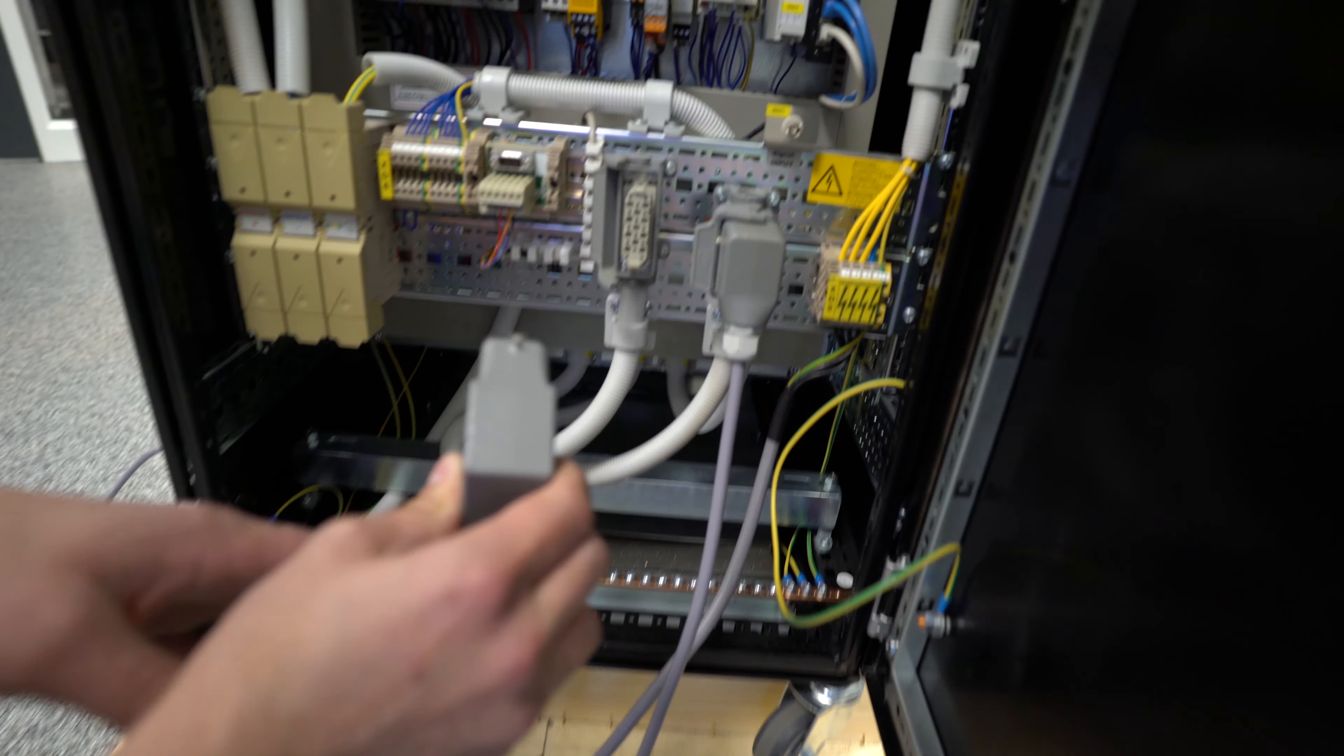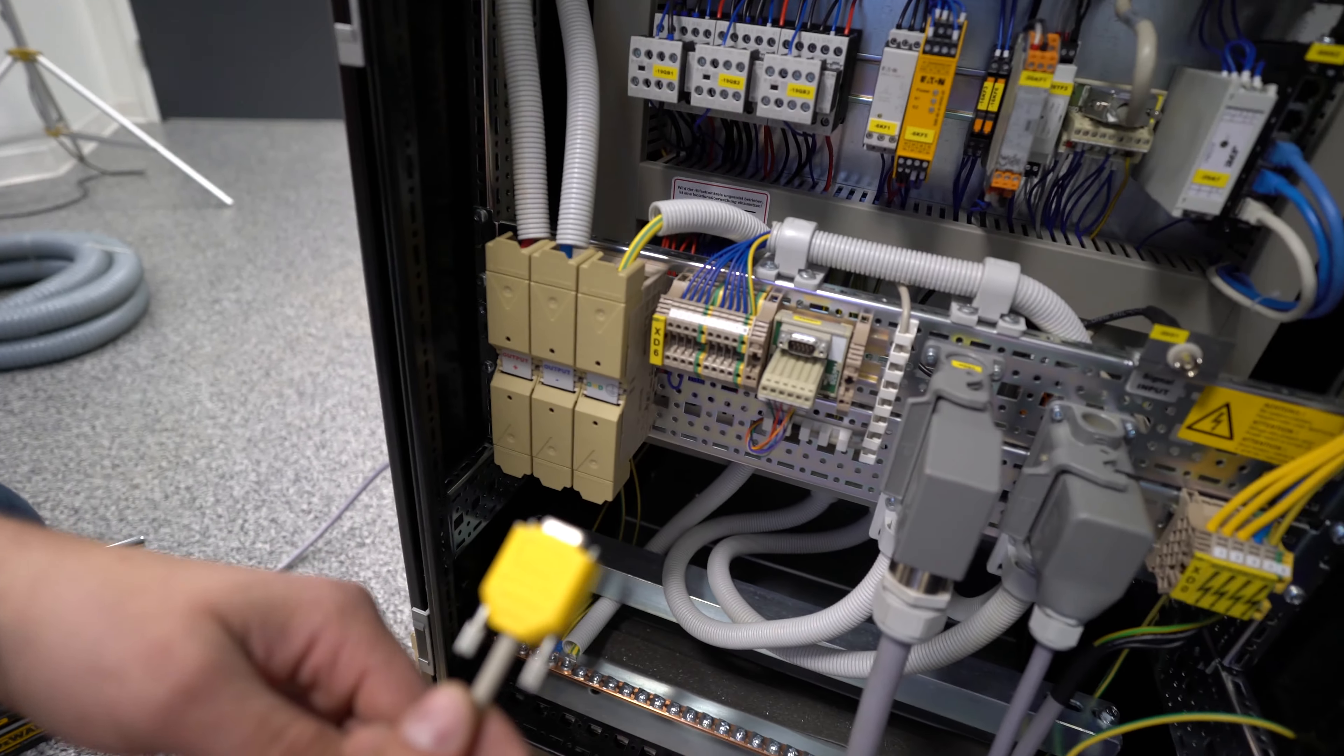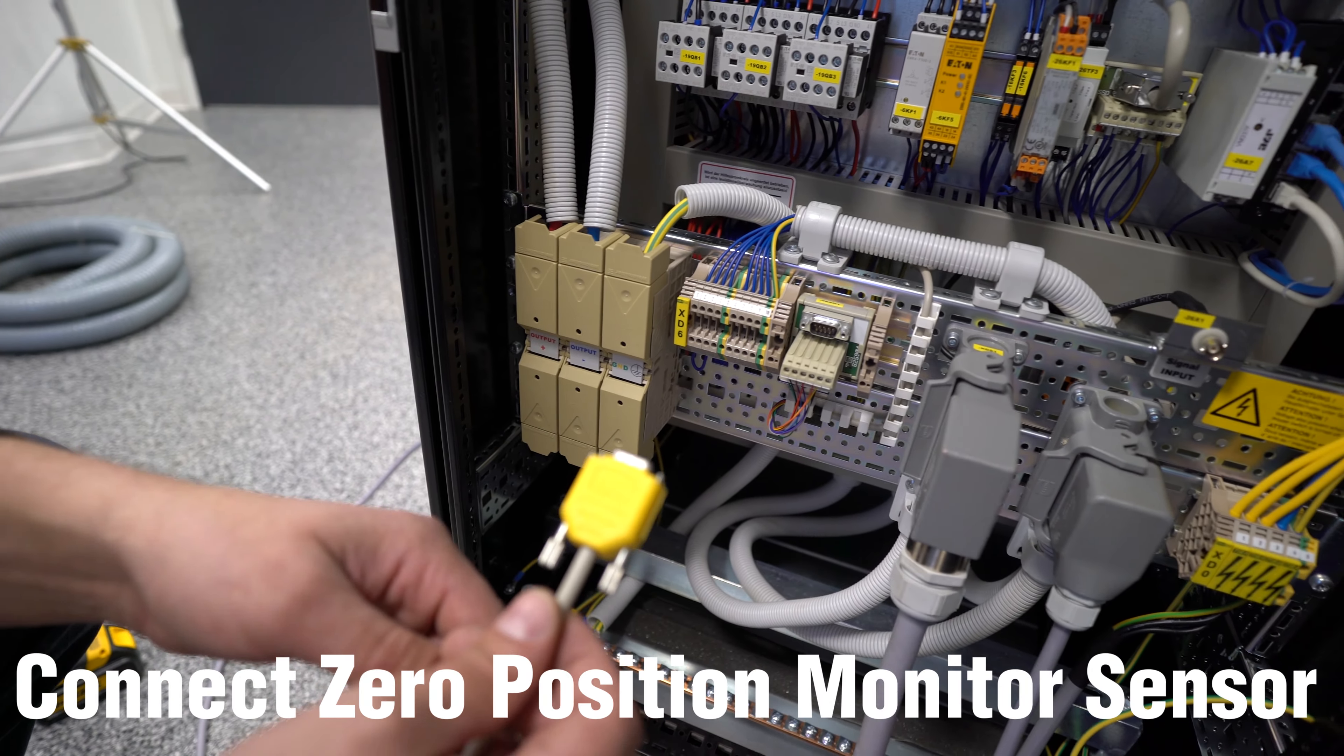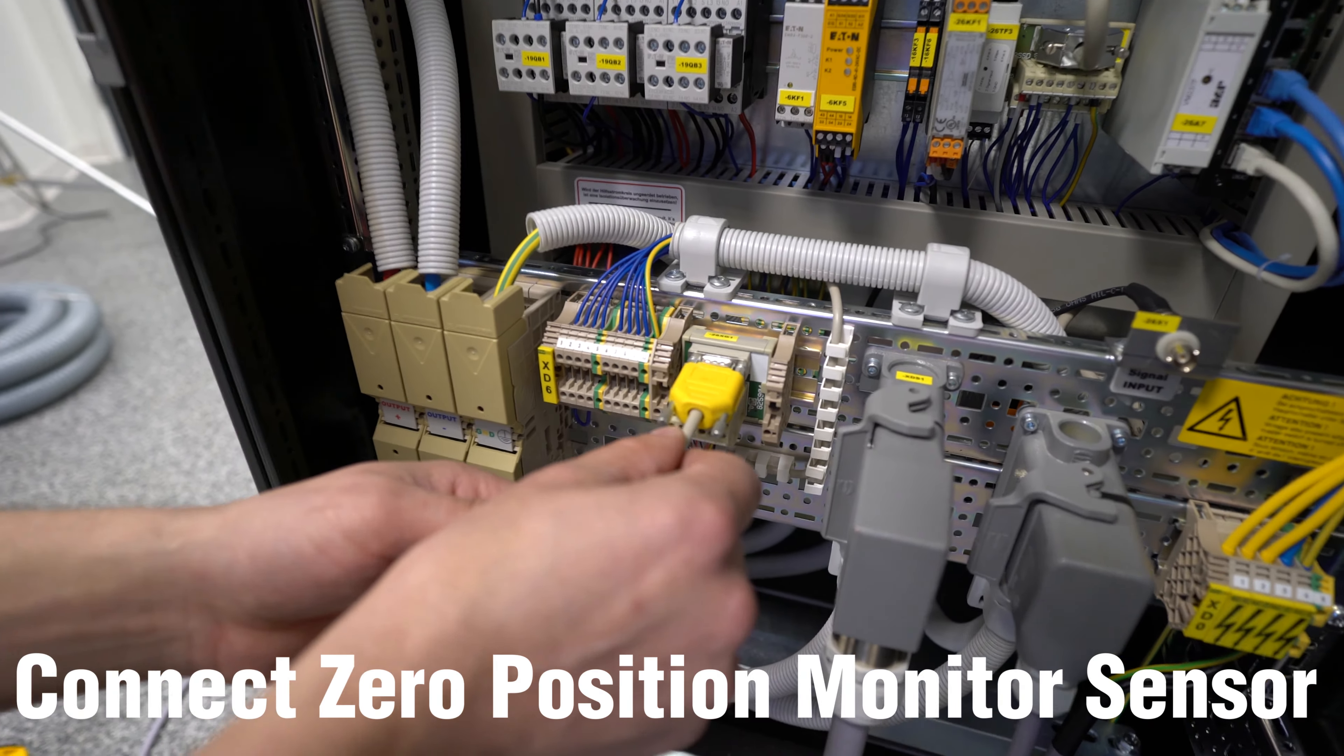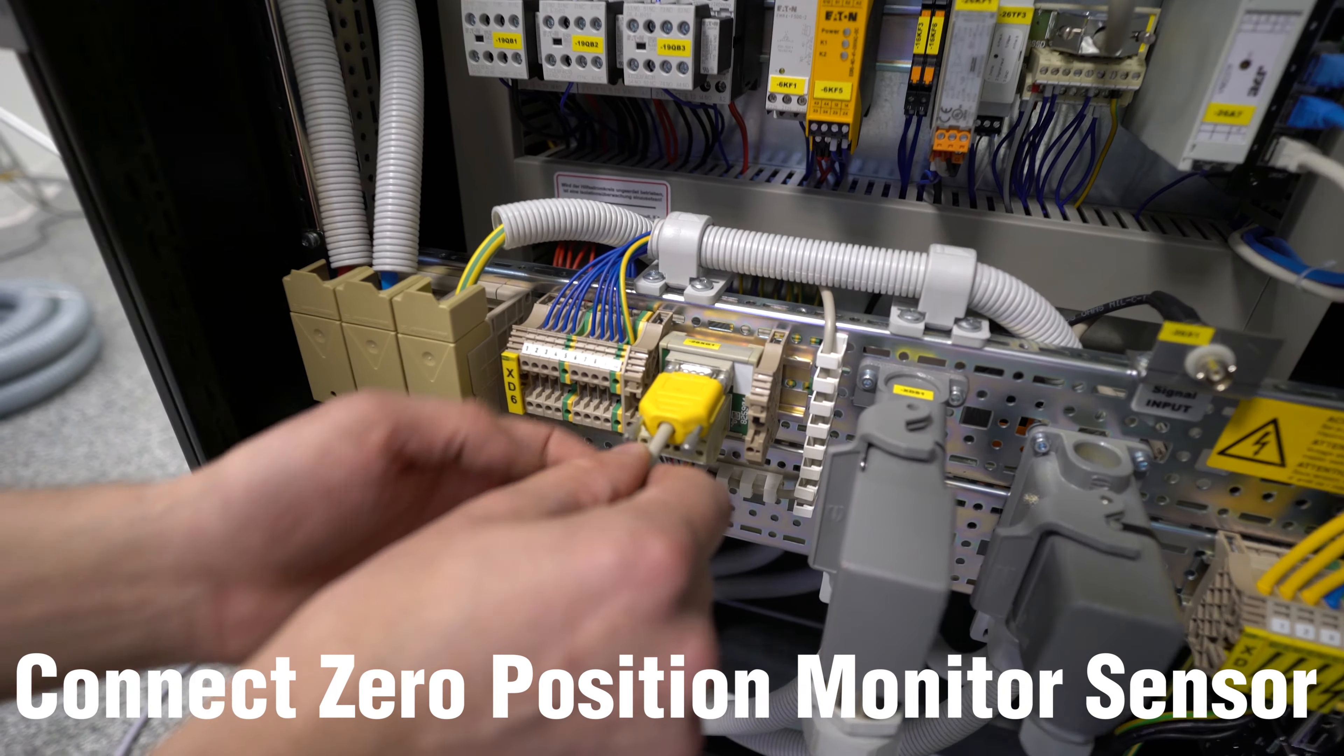The second connection that we're going to make for the shaker is going to be the zero position monitoring sensor. It plugs in right here. We'll thread those in.